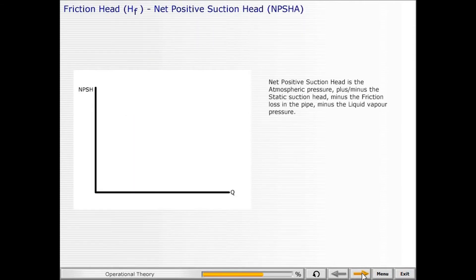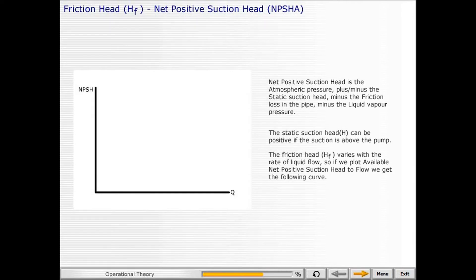Net positive suction head is the atmospheric pressure, plus or minus the static suction head, minus the friction loss in the pipe, minus the liquid vapor pressure. The static suction head can be positive if the suction is above the pump. The friction head varies with the rate of liquid flow, so if we plot available net positive suction head to flow, we get the following curve.